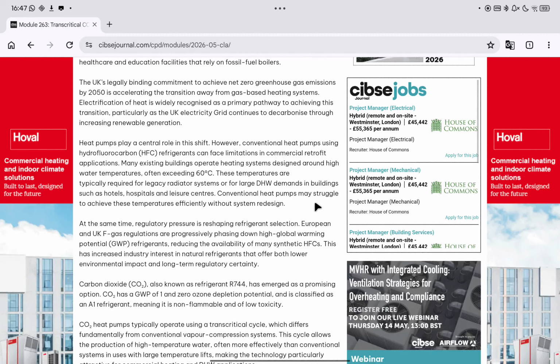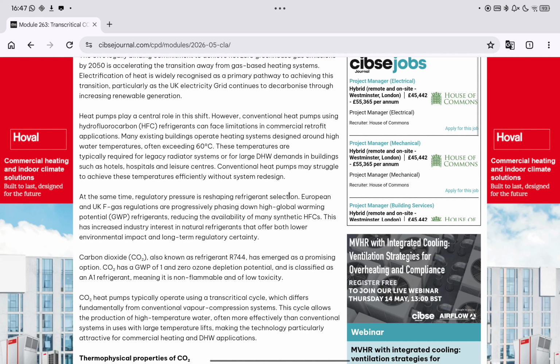At the same time, regulatory pressure is reshaping refrigerant selection. European and UK F-gas regulations are progressively phasing down high global warming potential, or GWP, refrigerants, reducing the availability of many synthetic HFCs. This has increased industry interest in natural refrigerants that can offer both lower environmental impact and long-term regulatory certainty. Carbon dioxide, or CO₂, also known as refrigerant R744, has emerged as a promising option.